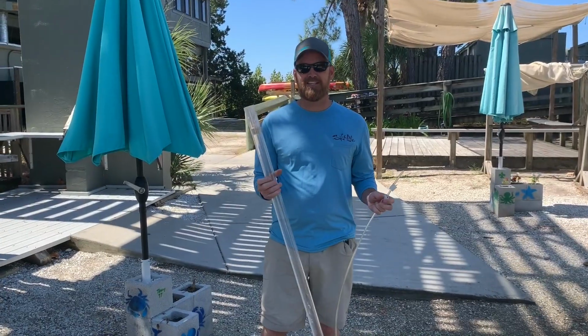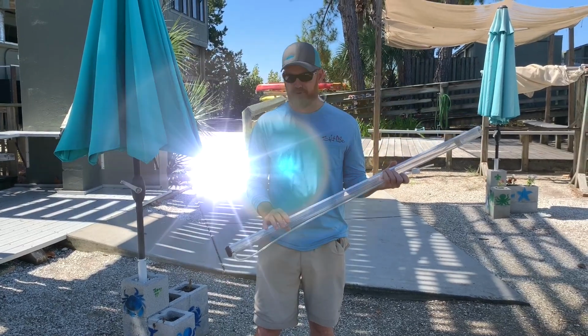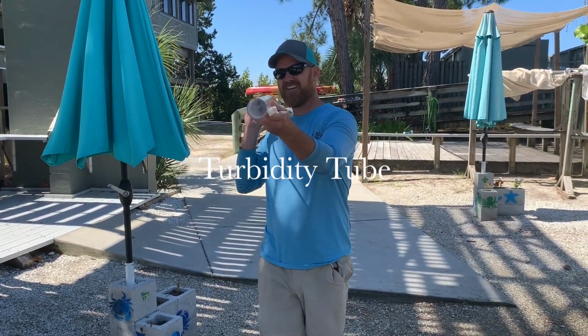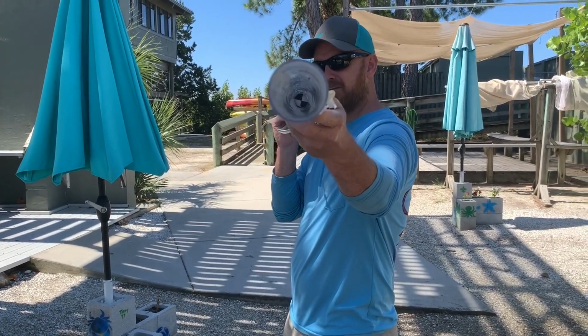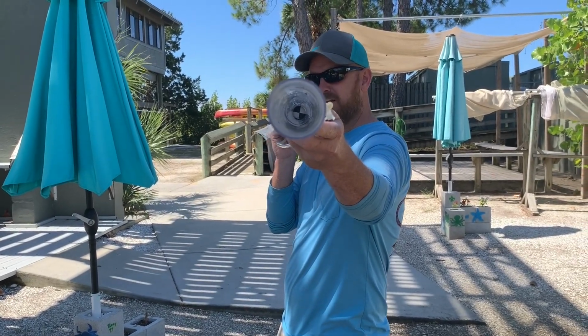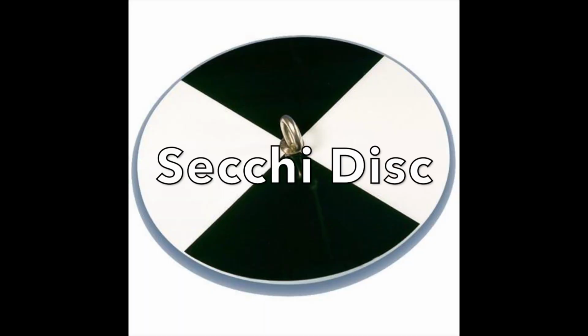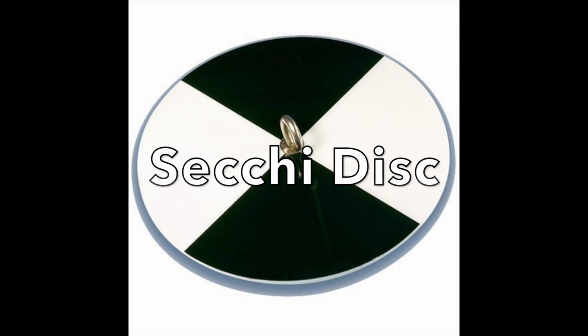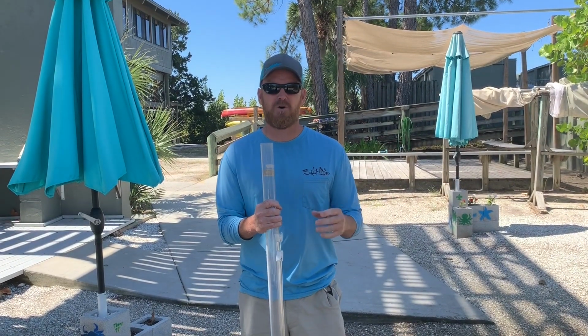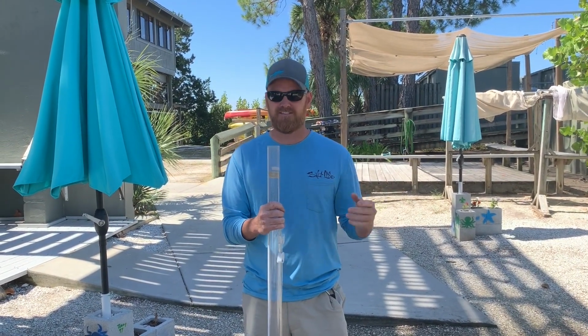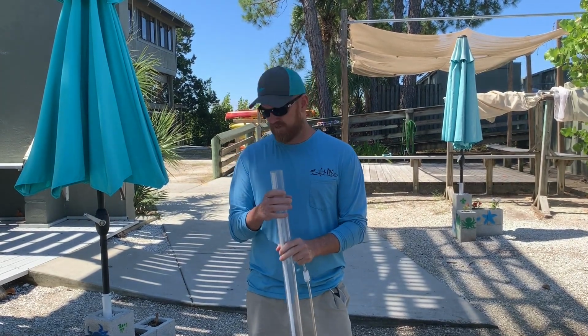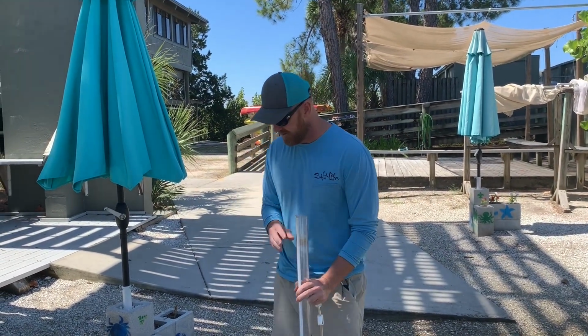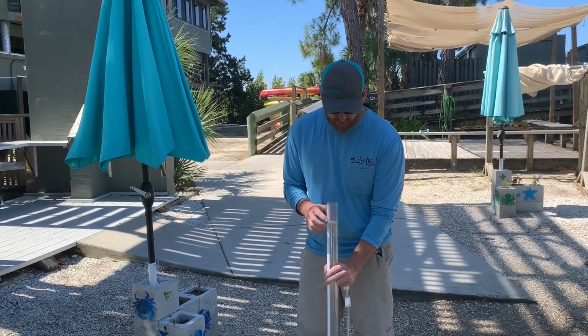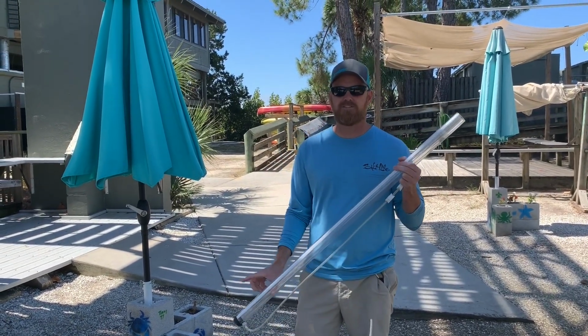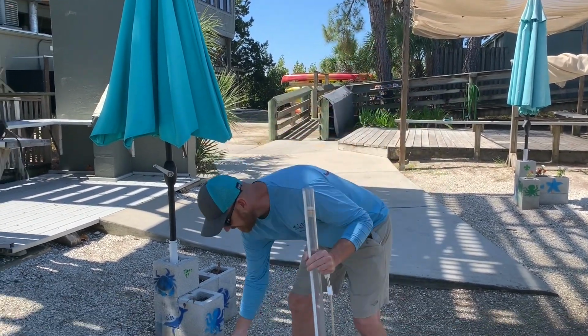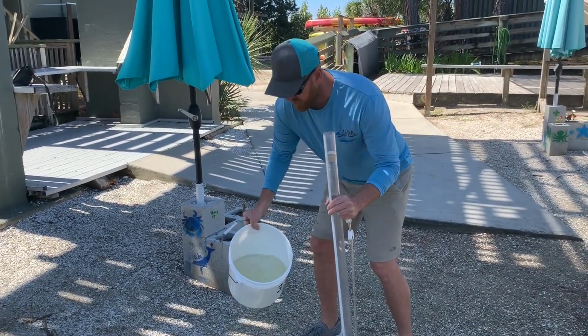The last test we're going to do is turbidity. We have what's called a turbidity tube here. And if you look down at the bottom of the barrel there, you're going to see this little black and white checkered disc. And so turbidity is the amount of suspended solids. It's going to be the clarity of the water, how murky or clear it is. And what we do is we pour water into the tube here until we can no longer look through and see that black and white checkered disc at the bottom. So I'm going to attempt to do that here by pouring water.